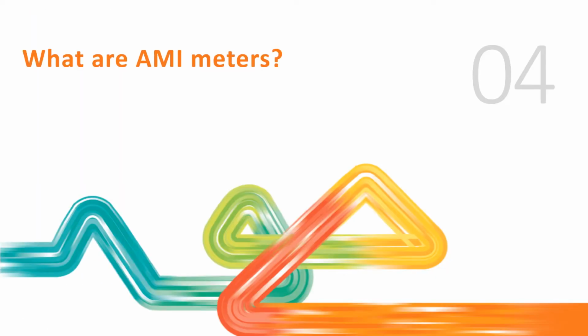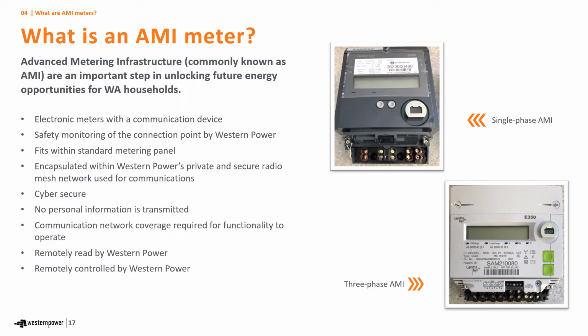So I've talked a bit about AMI meters. AMI, advanced metering infrastructure, are an important step to unlocking future energy opportunities for WA households. It's an electronic metering device which has an embedded communication device. Western Power uses this for safety monitoring of the connection point. It fits within a standard metering panel, and it's connected to Western Power's private and secure radio mesh network, which we use for communications. Being a private network, it gives a high level of cyber security, and there's no personal information transmitted across this network.